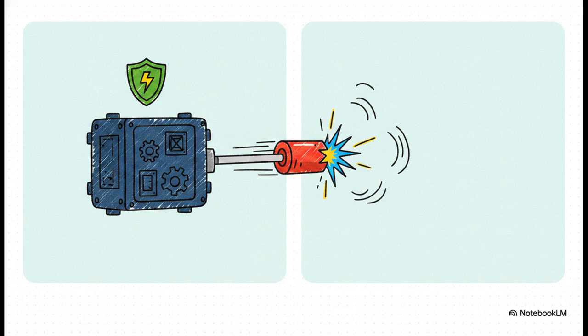Now, check out this deliberate mismatch on the specs. Did you catch it? The contactor is rated for 400 amps, but the associated fuse is actually rated lower at 315 amps. This is definitely not a typo. The fuse needs to clear a short circuit incredibly fast and cleanly, well within the contactor's 400 amp thermal and mechanical limits, before the contactor itself can take any damage.